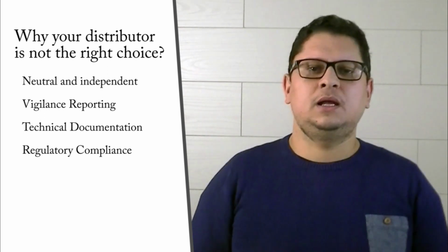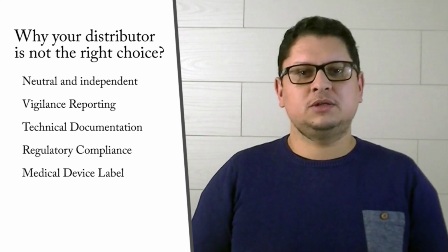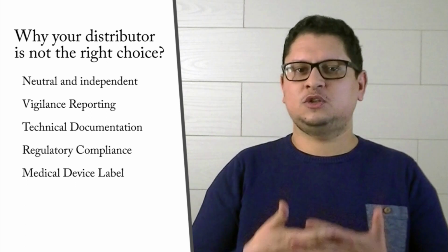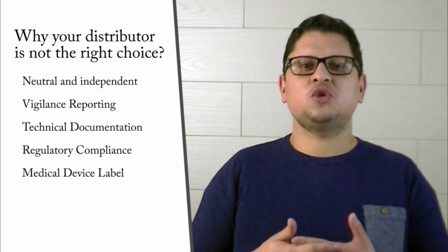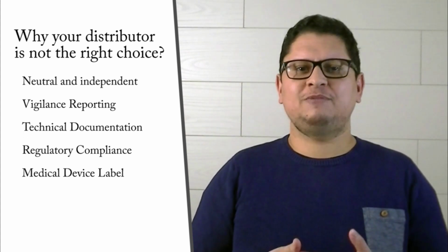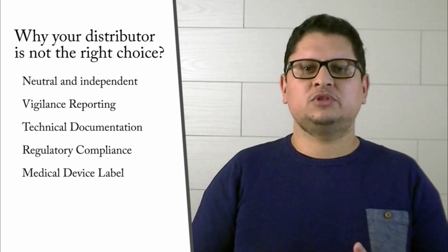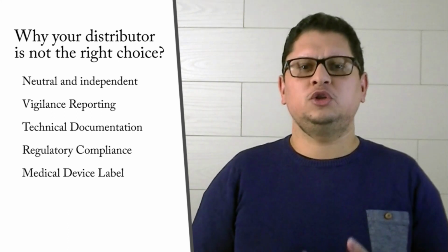And last but not least, the name of the distributor will be on your products, because he's your European Authorized Representative. What does it mean? It means that if you have any conflict with your distributor, and you want to change the distributor, you will then have to change all your packaging. You may have to scrap some products. You may have to take a lot of actions that will cost you a lot of money. So it is really important to think about it before choosing your distributor as your European Authorized Representative.